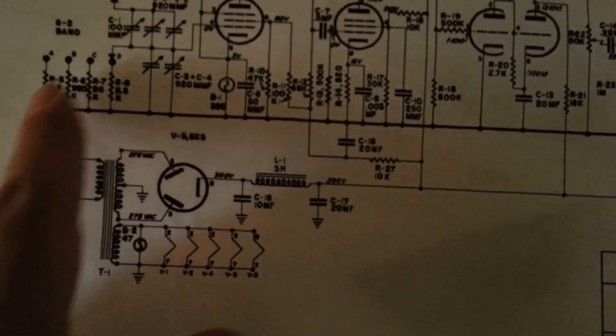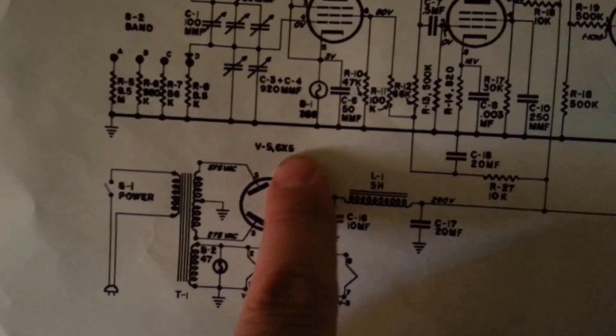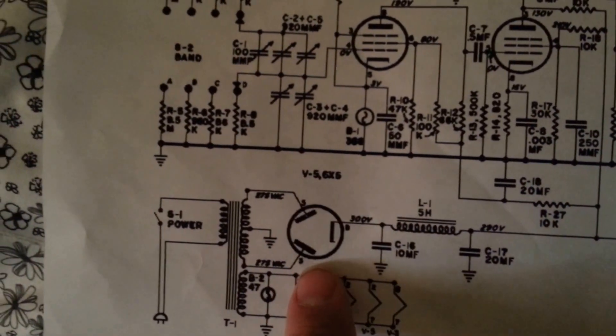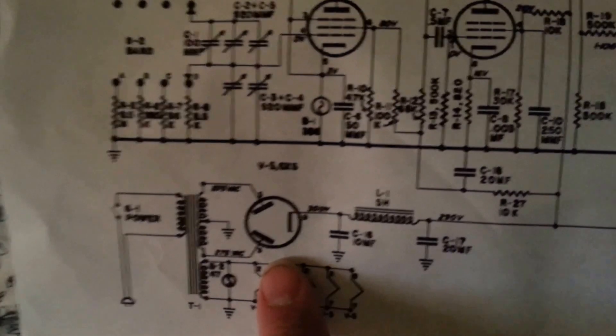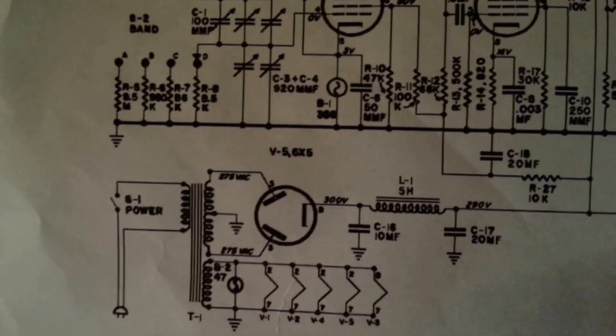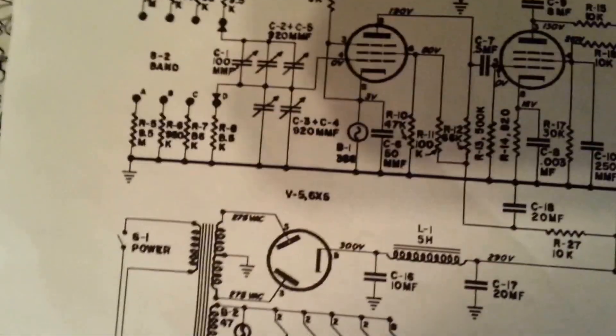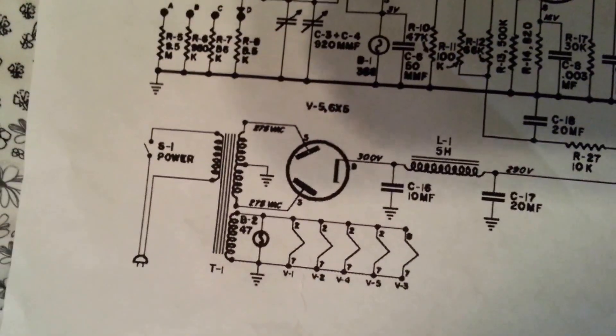And this right here is your power supply. This tube, which in a lot of applications is a trouble tube, is really considered a trouble tube at least in the older tube designs because they have been known to have filament cathode shorts and destroy the filament transformer.